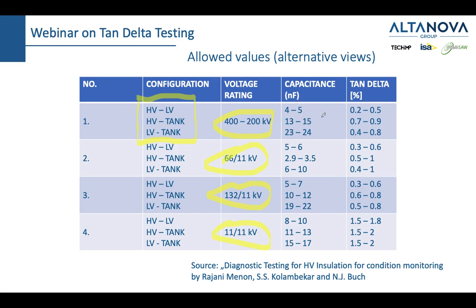And capacitances for a power transformer are expressed in nanofarads, and capacitances for bushings are mostly expressed in hundreds of picofarads. Now, when we talk about, let's say, a medium voltage transformer, then we see that the high voltage, low voltage tan delta is between 0.3 and 0.6, but high voltage tank and low voltage tank can go up to 1%. Then, I would say a standard high voltage transformer, 132 to 11, would be between 0.3 and 0.6 for high voltage and low voltage. And between high voltage and tank and low voltage and tank, you could have a little bit more margin. And then last but not least, would be a distribution transformer.